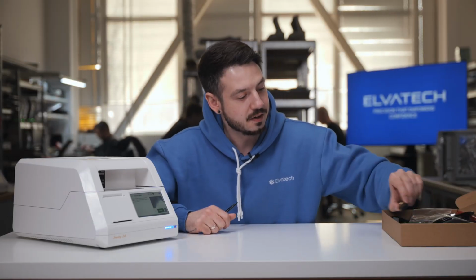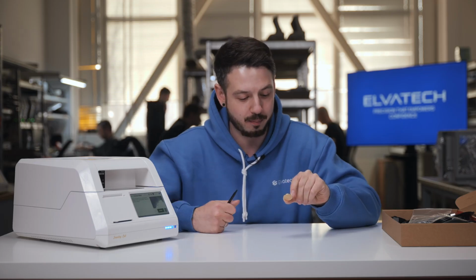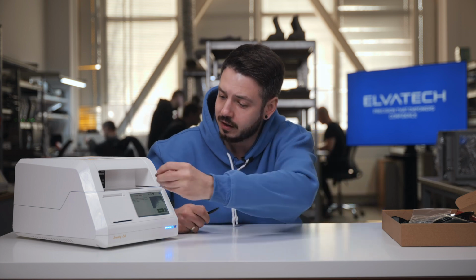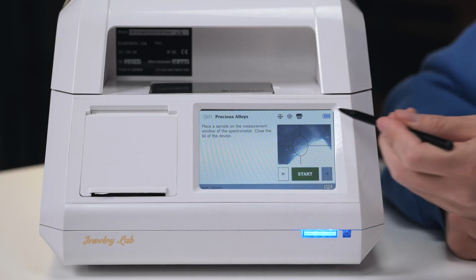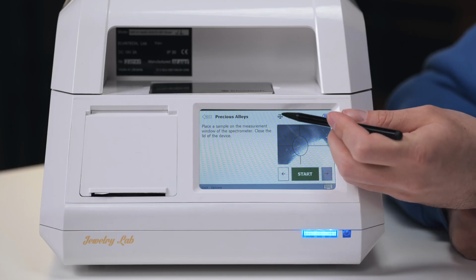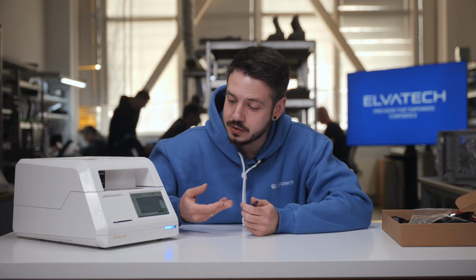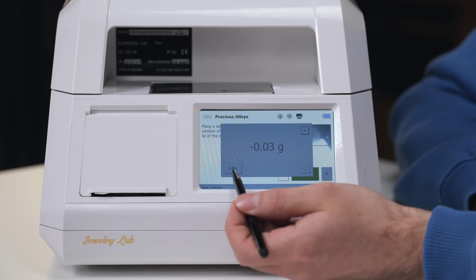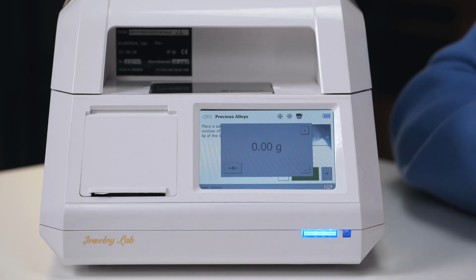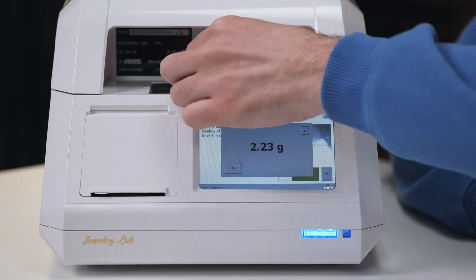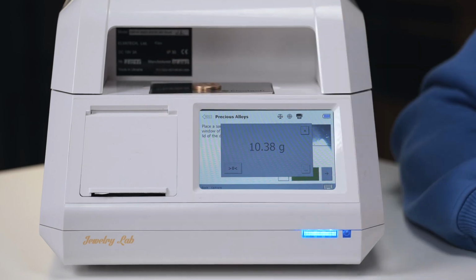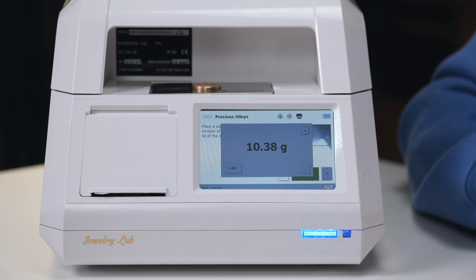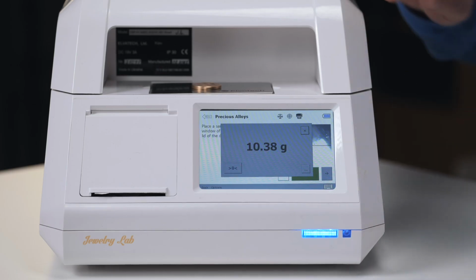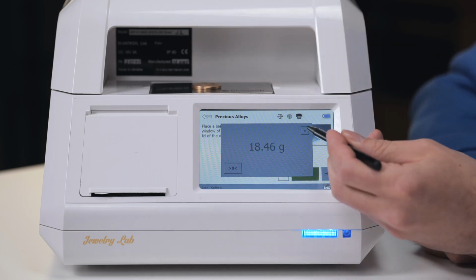And let us take the sample from our consumables box, and we're gonna stick with this one because it's probably the bronze sample, and that's what we actually need for the precious metals calibration. Alright, first of all, we need to press the special icon on the display, so it says weight. And then we need to just reset our weights to 0. So let's just calibrate it a bit. That's it. And now we will have a clear measurement of the weight of this sample. And we have it just a little bit over 10 grams. Right, that's good. Then we press back here.